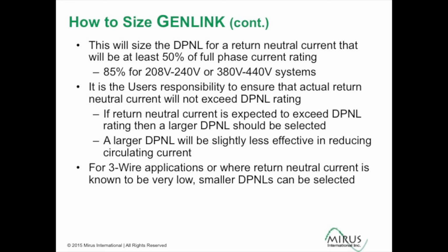So if you have a lot of phase to neutral loads and you're expecting the return neutral current to be higher than 50% in the typical power system applications, or higher than 85% in the 208 to 240 or 380 to 440, then you might need to go one size up on the DPNL to handle that. But certainly, by far the majority of the applications, the standard ratings for neutral return current are more than acceptable. For 3-wire applications where there's no return neutral current, we can definitely select smaller DPNLs.